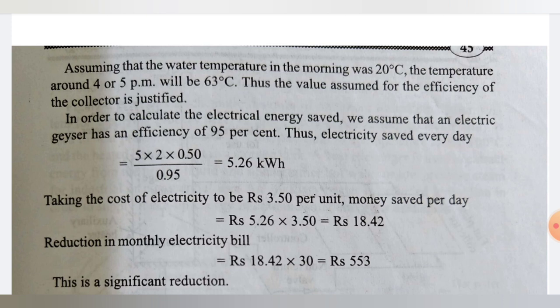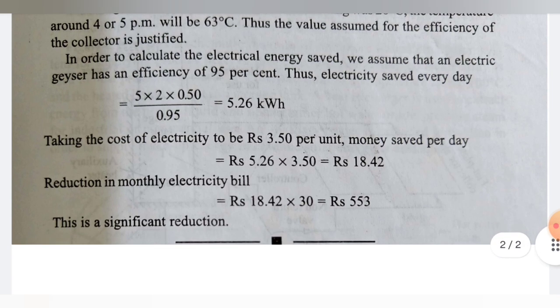In order to calculate the electrical energy saved, we assume that an electrical geyser has an efficiency of 95 percent. Thus electricity saved every day equals 5 (kWh) × 2 (m²) × 0.50 divided by 0.95, which gives 5.26 kilowatt-hours.